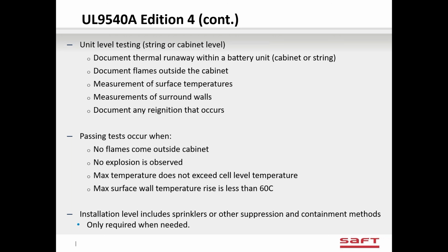But the test is actually not a pass-fail test. It is a test method and a report that's generated that tells you all of the temperatures and whether or not you got propagation, whether or not you got explosion, whether or not you got flame outside the cabinet. It tells you what the maximum temperatures were on the outside of your cabinet and on the surfaces of the walls around the cabinet. It's a test report.